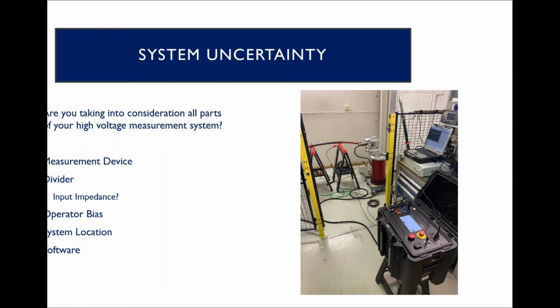While there are other items that may also contribute to your total system uncertainty, I would like to touch on software's effect. Software should always be validated to ensure that it is not introducing additional error into your measurement. For example, if your software is not reading at appropriate times for your measurement or for your measurement device, or is performing some additional averaging, the uncertainties that may have been previously calculated based on everything else could be invalid just due to how those measurements are being performed through the software.